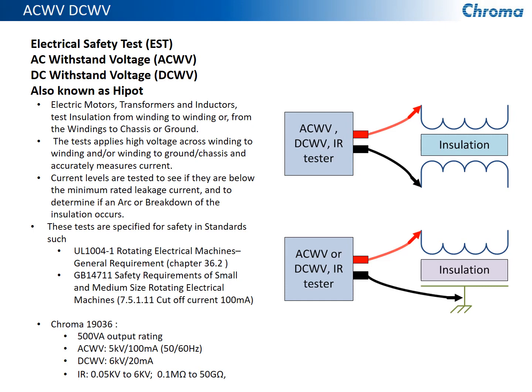When you do this test, you normally apply the high voltage, you measure the current, and you look for excessive leakage current that's usually measured as an RMS value. But in addition to that, we've added the ability to also measure short transients, peak current measurements that would indicate either a breakdown or arc or flashover. So this is also a separate test that can be detected at a peak current, and we can set the parameters for that as well for pass-fail.